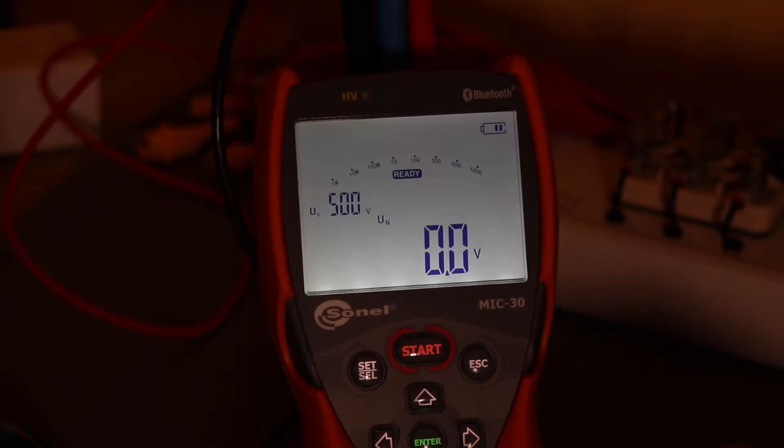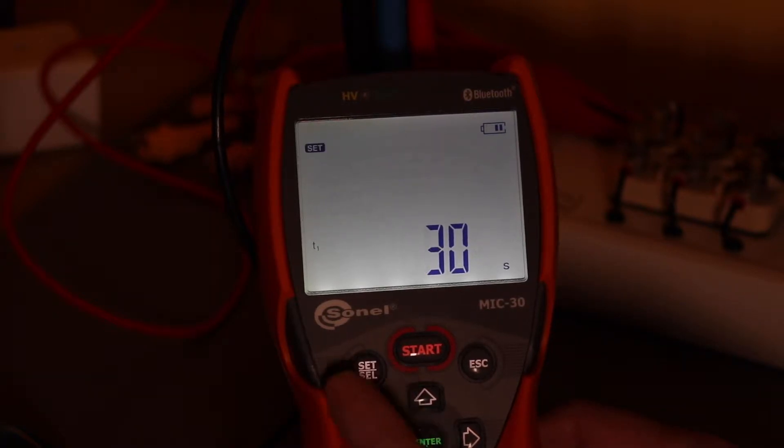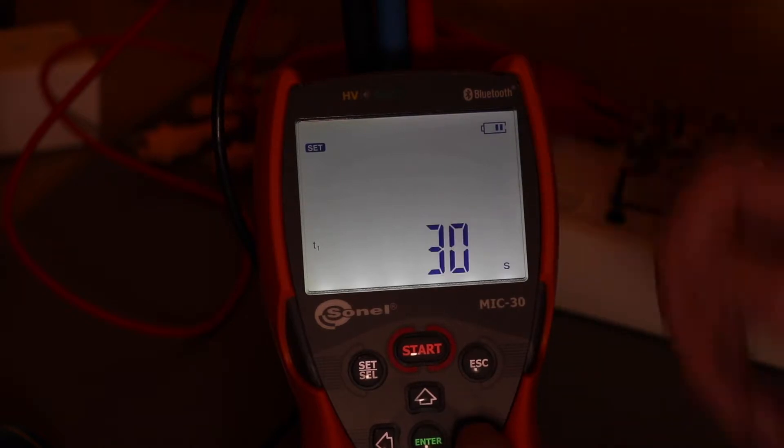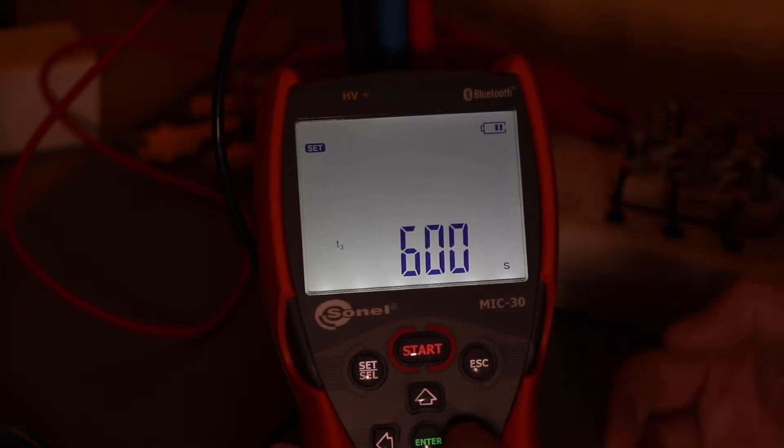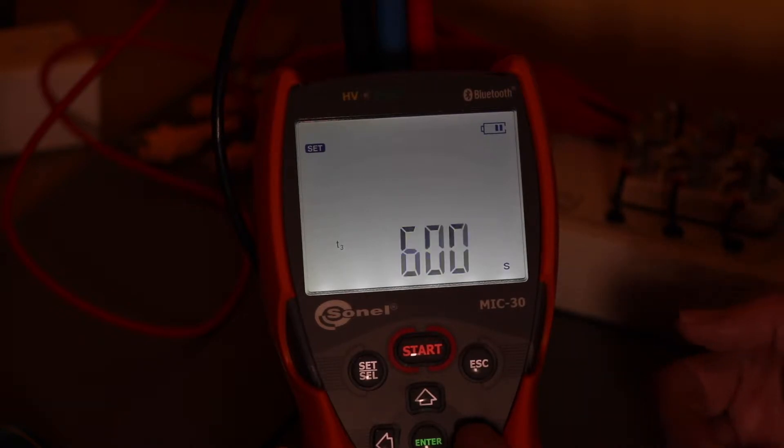First thing I'm going to do is set up the timestamps that this meter has, whereas the other insulation testers have specific DAR and PI buttons to select those ratios. This meter doesn't have that. What it does have, if I hit the set button, is three timestamps. So the first one is 30 seconds, 60 and 600. So that's set up for a standard DAR test and PI test.